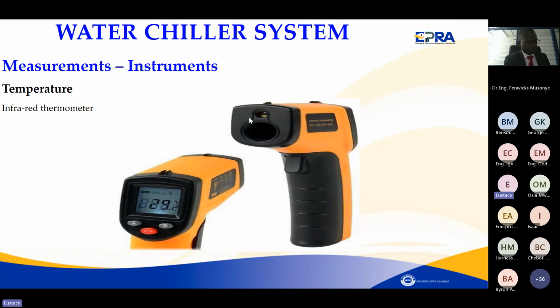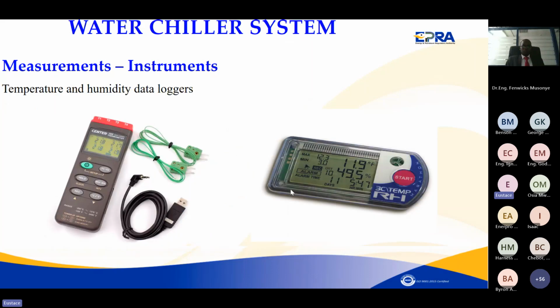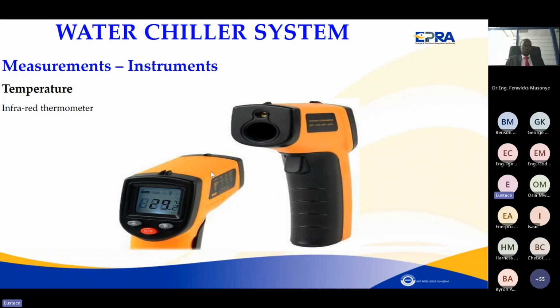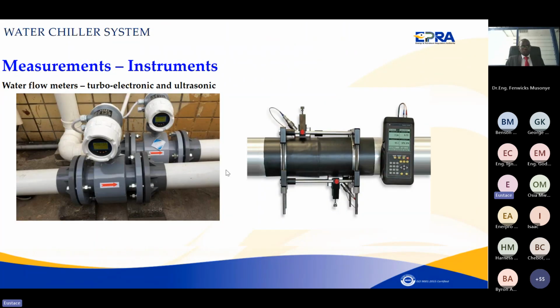You can get infrared thermometers to counter-check whatever you've logged. As we said, it's good to measure within the cycle, but you won't be able to be there throughout, so you use loggers, then counter-check or calibrate with infrared thermometers. You need flow meters, ultrasonic ones, to check whether the fixed meters are working well—though fixed meters are the best. Ultrasonic meters are just for checking, or used where you don't have meters for comparison; they're not as accurate as turbine meters.